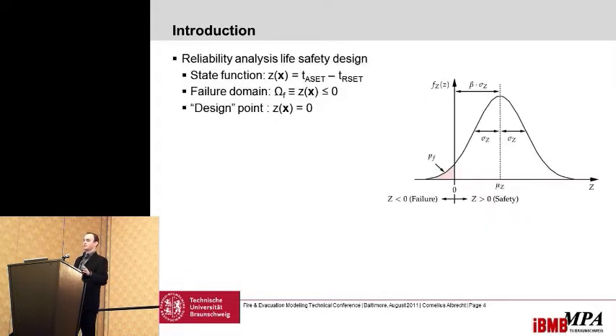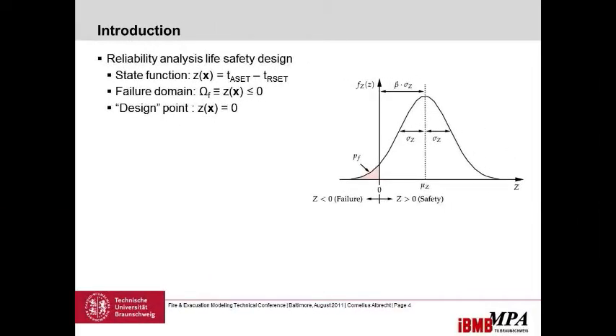To do reliability analysis, we need a state function — here it's simply the available safe egress time minus the required safe egress time — and a failure domain omega_f, which is where the state function falls below zero. The failure area is where the required safe egress time becomes greater than the available egress time. I also want to find the design point at zero, because that's the optimized solution: to the right I'm overly safe, to the left I'm not safe enough.